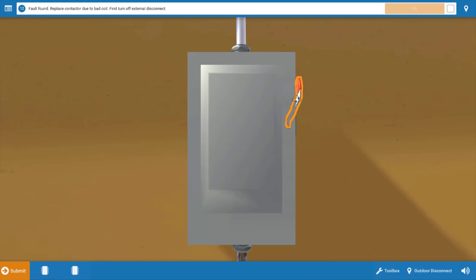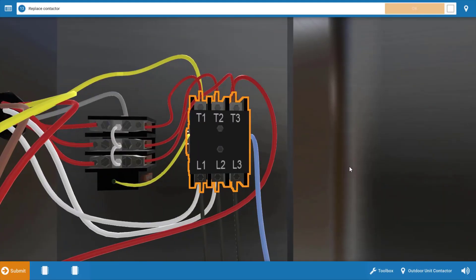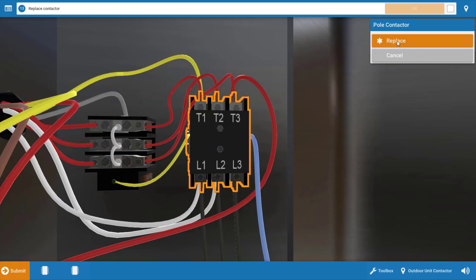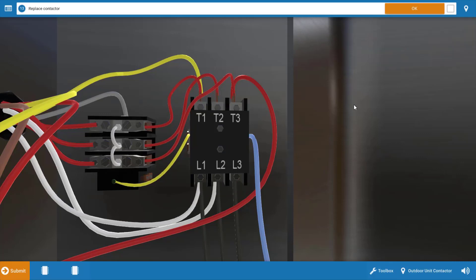So we're going to turn the disconnect off, click OK on the procedure guide, and we're going to replace the contactor. Now, on some larger contactors, you can replace individual components inside. So in that case, it would be necessary to do a resistance check of the coil to determine that the coil is at fault and not necessarily the actual contacts themselves. But in this contactor, it's small enough where it's just replaceable. It's not repairable. So since we had 24 volts to the coil, and we verified that the contacts are not pulling in, we're going to replace the contactor. Click on it, click replace on the menu, and we've replaced the contactor and solved the problem.